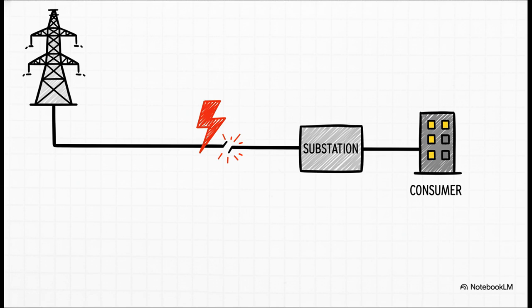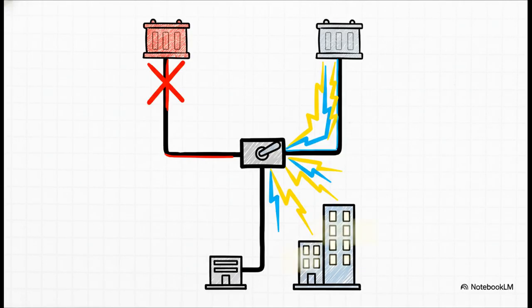End of story. So the next logical step up is the primary selective system. The big idea here is redundancy. You add a second power source from the utility and a switch. Now, if your main line fails, you can just flip over to the backup feed. This cuts your potential downtime way down.